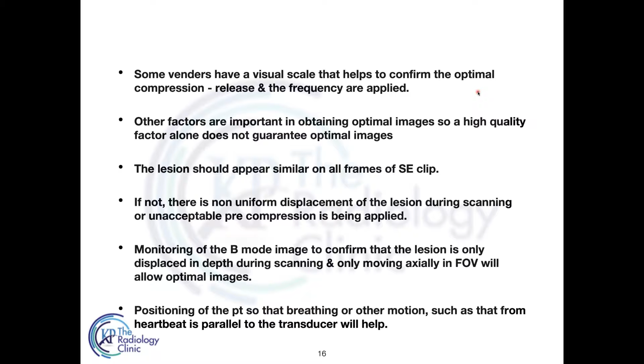The compression release should be orthogonal to the plane, perpendicular to the lesion. I'll show you an image also. Monitoring of the B mode image to confirm the lesion is only displaced in depth during the scanning, moving only axially in the field of view, will allow for optimal images. Position the patient so that breathing or other motions, such as from the heartbeat, are parallel to the transducer, and they will be negligible and not interfere.